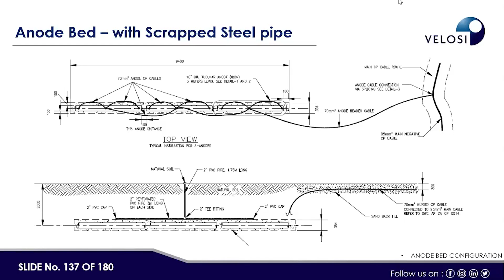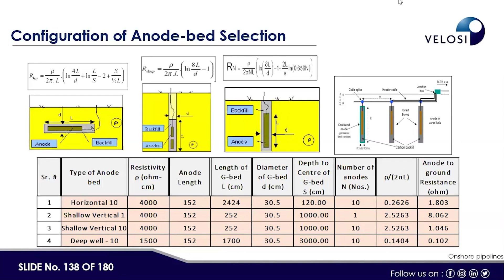The designer generally checks all types of anode beds. If you go with a surface horizontal ground bed, the resistivity is high. The deeper you go, the resistivity comes down because there's more moisture. So if you install a deep well anode bed with 10 anodes compared to a horizontal anode bed with 10 anodes, you can see the difference in resistance. The horizontal ground bed gives about 2 ohms resistance, while the deep well gives about 0.10 ohm. Lesser resistance is more beneficial for the ground bed and works faster. So from here we can judge which option is more economical, though deep well obviously requires deep boring and drilling.